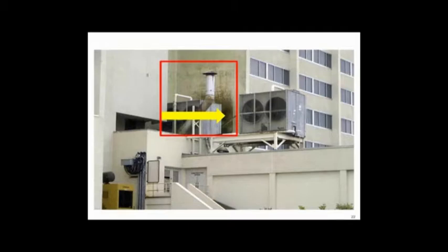And to make matters worse, what do you think that exhaust pipe is above the tower? That is the natural gas exhaust for the laundry. If you got natural gas products going out the top, warm, moist air going round and around and around, you got carbonic acid in the tower. So the tower lasted about 6 months, ate away, tore it up, would not get rated capacity, and it ain't my fault. And you guys have got to begin to realize there's some common sense here. You've got to have a little common sense, and you got to start recognizing problems like that. Very common, everyday issue with towers that you should at least use a little common sense when you're looking at one.